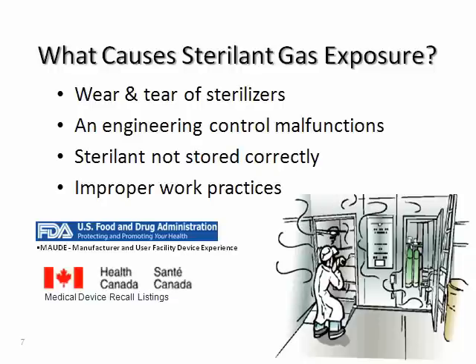What if any of these would happen in your facility? A leak in the exhaust hose behind the sterilizers. An exhaust fan, damaged during a lightning storm, forces ethylene oxide gas back into the work area instead of outside. Difficulty breathing while a hydrogen peroxide sterilizer is running. Or even a leaking ETO canister inside the fireproof box. All of these have happened. And without some means to monitor in place, these incidents may have gone undetected, or more importantly, not corrected soon enough to protect employees from exposure.